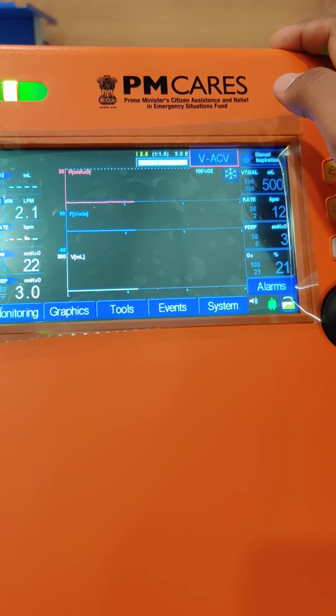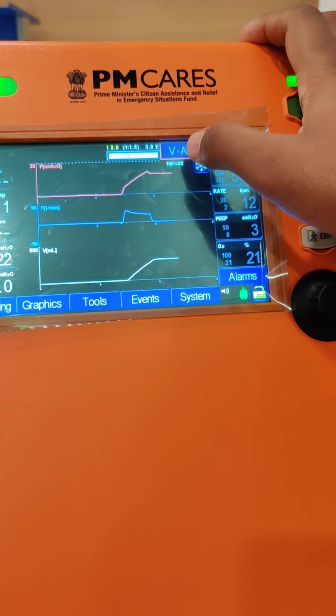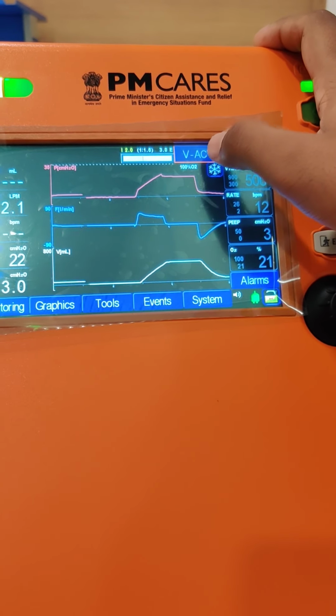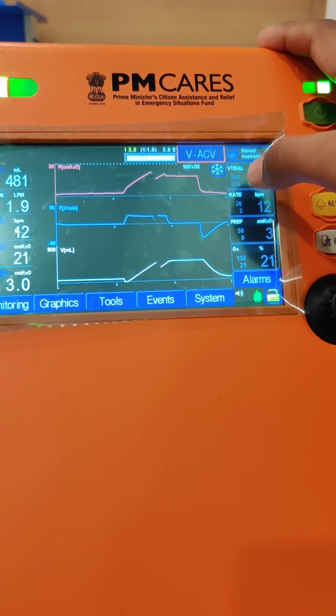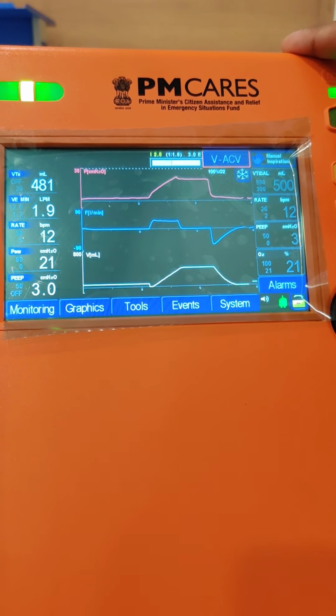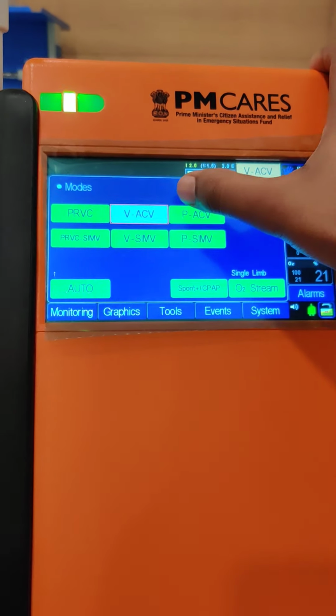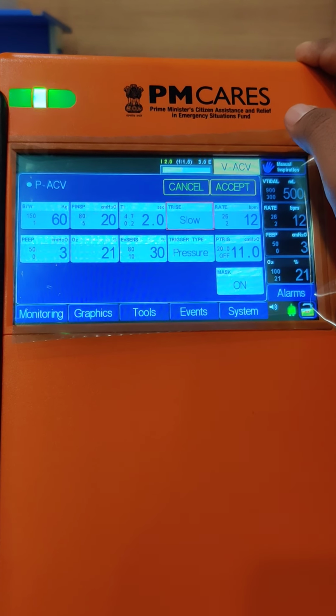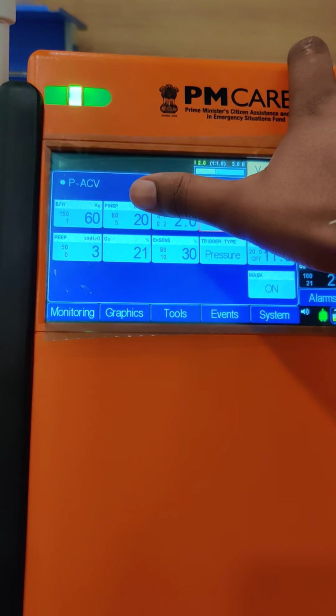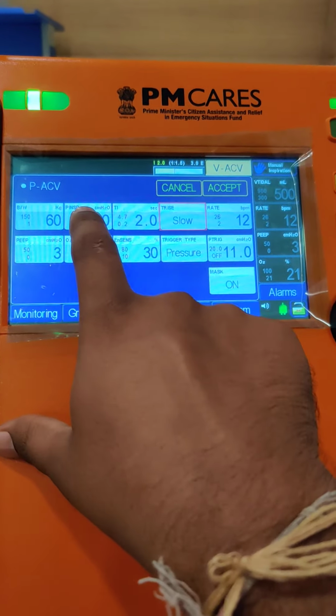So now the ventilation has been started in VACV mode, and it is displaying over here that VACV mode of ventilation is activated with all these parameters. Then we have this pressure assist control ventilation. Here you will be doing the setting of the inspiratory pressure, P inspiratory.